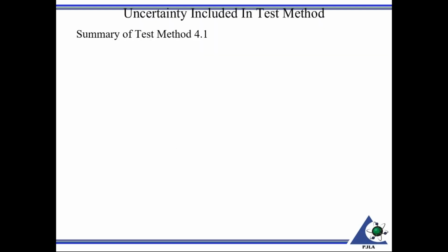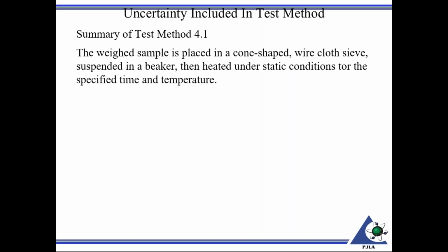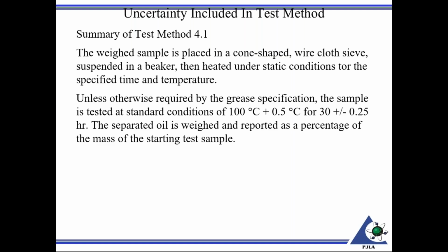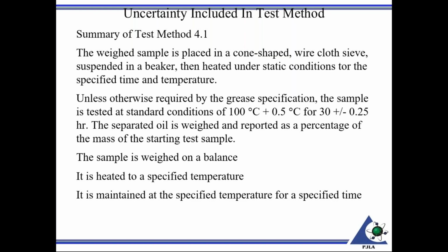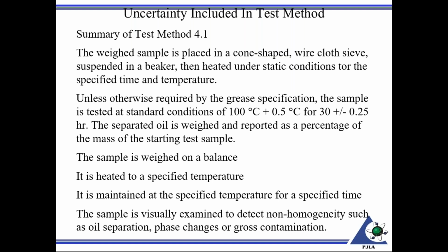So again, the summary of the test method: we're not deviating. We have to assure that the weighed sample is placed in a cone-shaped wire cloth sieve suspended in a beaker and then heated under static conditions to the specified time and temperature, unless otherwise required by the specification. The sample is tested at standard conditions of 100 degrees C plus or minus 0.5 degrees for 30 hours plus or minus 0.25 hours. The separated oil is weighed and reported as a percentage of the mass of the starting test sample. The sample is weighed on a balance, heated to a specified temperature, and it must maintain that temperature for a specific time.